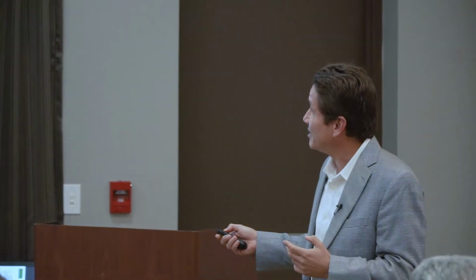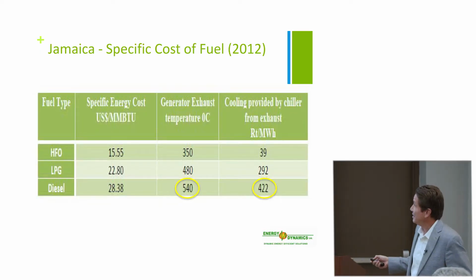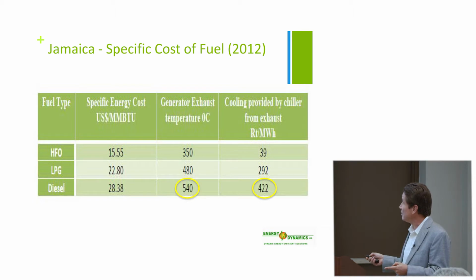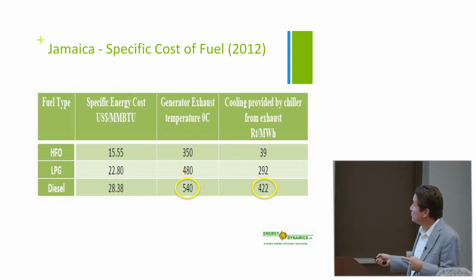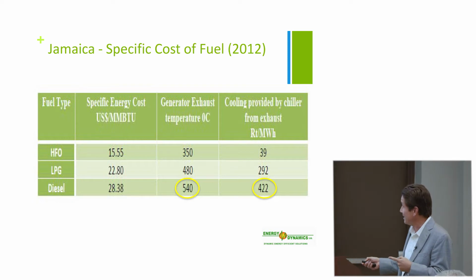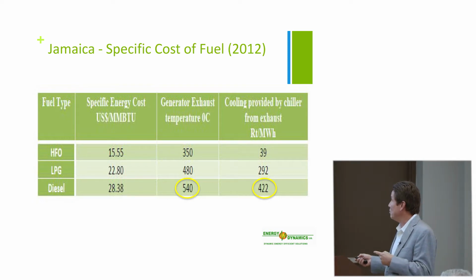And then the generator exhaust, this is something you need to know as well. If you run a generator on HFO, the exhaust temperature will be about 350 degrees Celsius, but that exhaust will only give you 35 tons per megawatt hour. If you run on LPG, you get 480 degrees Celsius, but only 292 tons per megawatt hour. If you run it on diesel, you get the highest exhaust temperature, 540, and you get more tons.